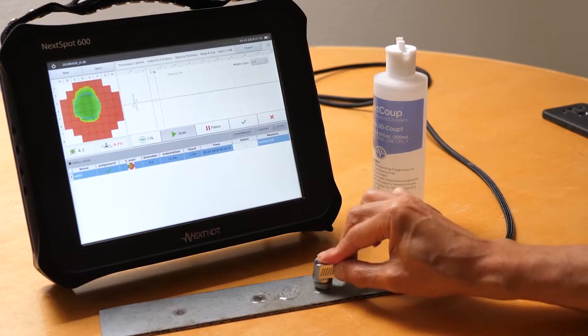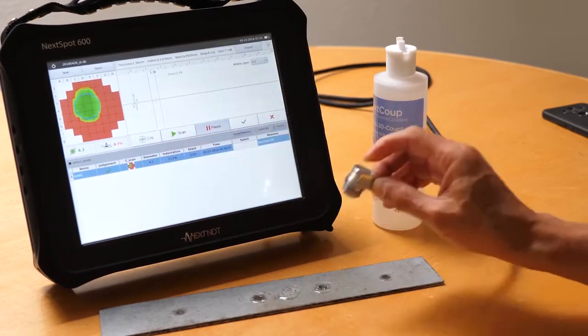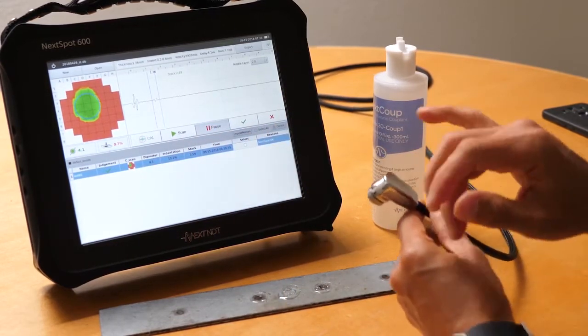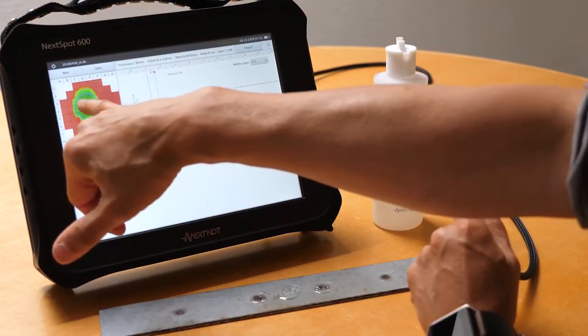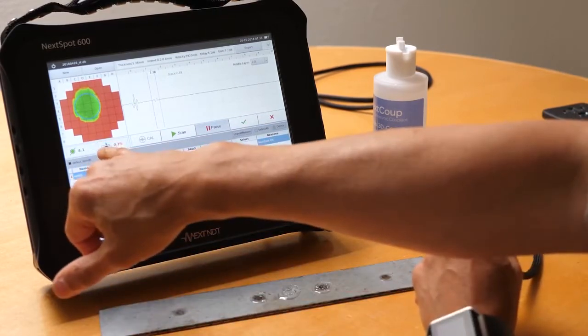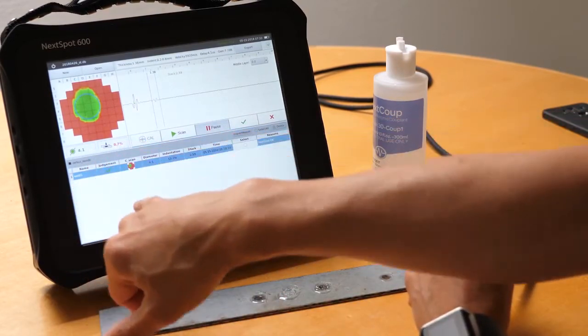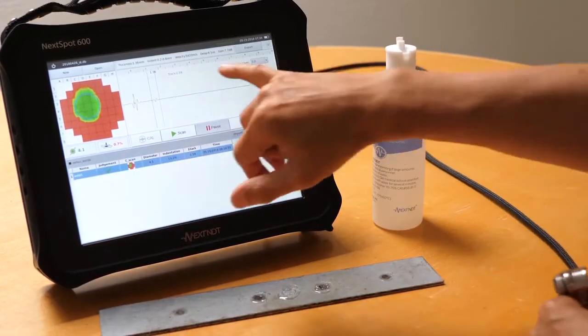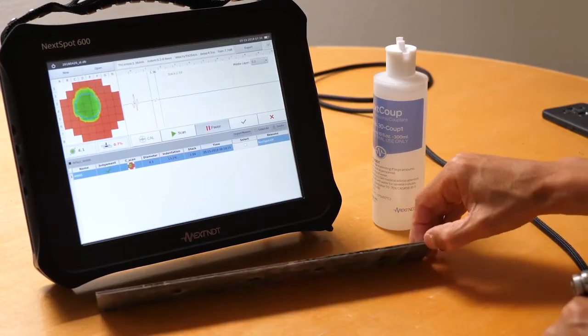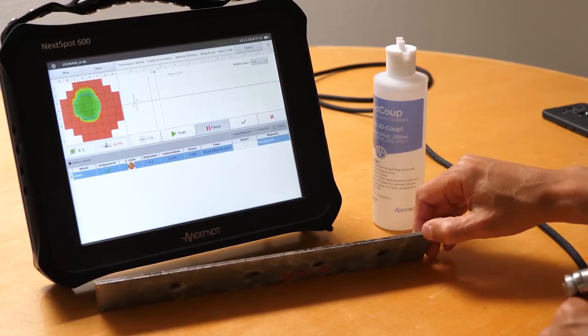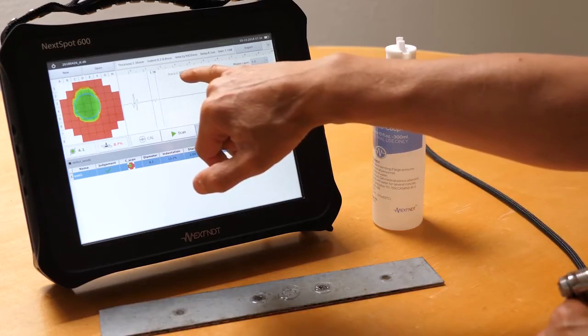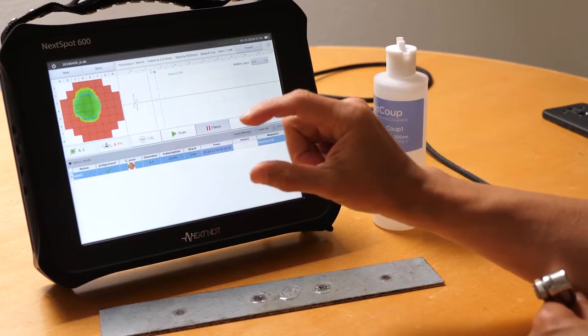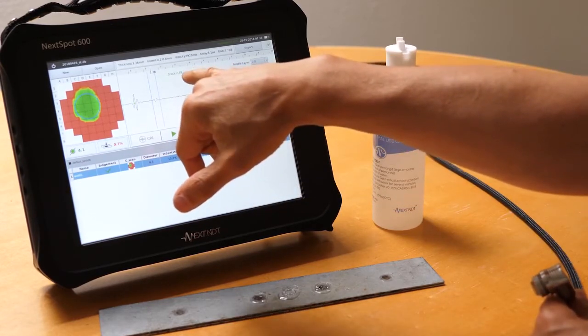Here we are on the first scan. I could pause it and this allows me to take a look at some of the data that I have. In this case right here, the diameter of the weld is 4.1, the indentation is 0.7. This number gives the thickness of the first sheet metal, and the stack here, which is the thickness of the nugget, is 2.59.